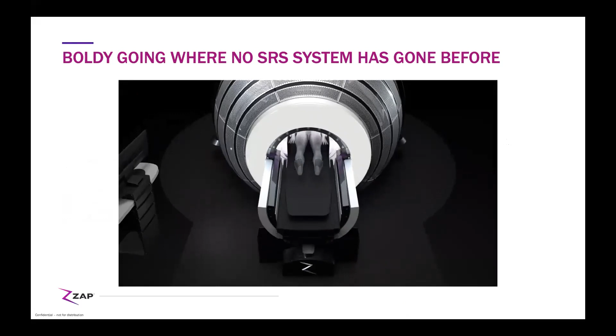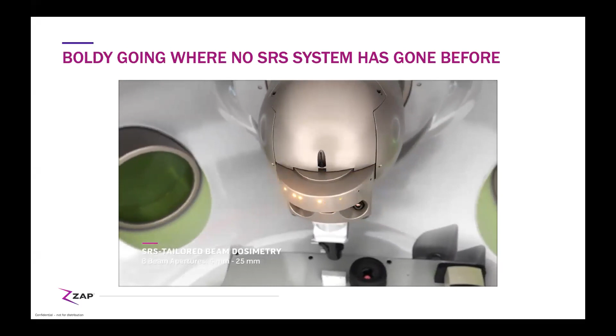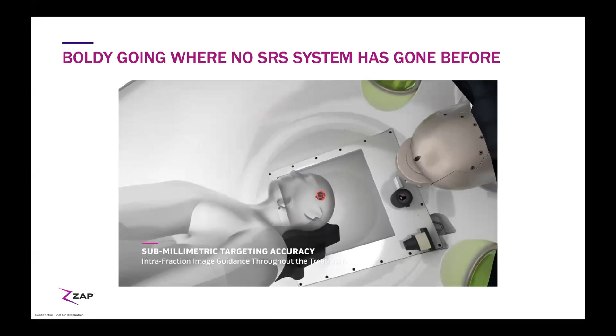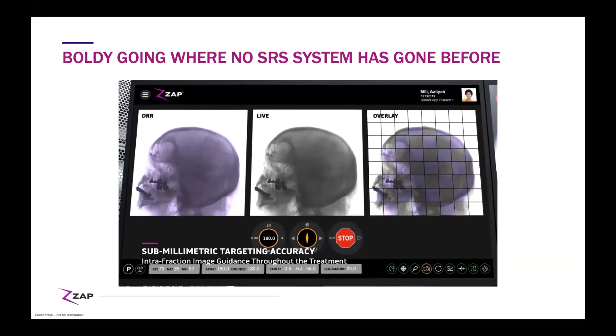And for those of you who don't believe, I urge you to get into ZAP-X soon and see for yourself. The collimation system is best in class, with minimal leakage, 50 times less leakage than you get with the best in class multi-leaf collimator. This spinning disc provides the beam shaping apparatus from 4 millimeters to 25 millimeters. You can have almost an infinite number of beam and aperture changes. The targeting system is X-ray image-to-image correlation using real-time digital imaging and correlating that against a digitally reconstructed radiograph, CyberKnife-like, but with a single X-ray projection over time.